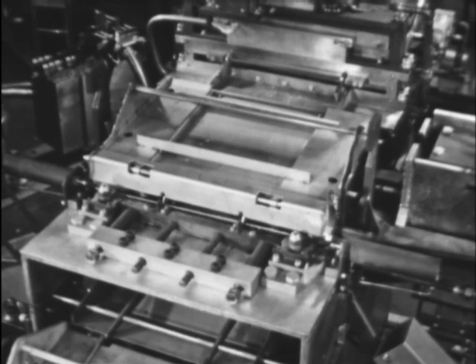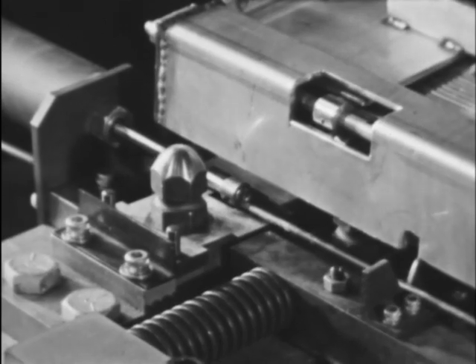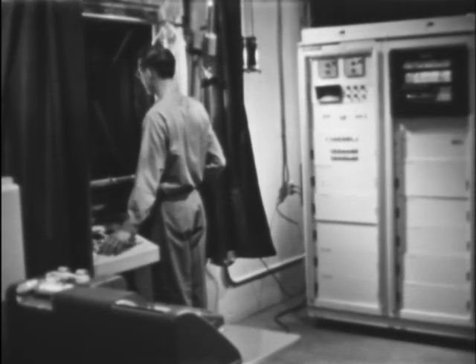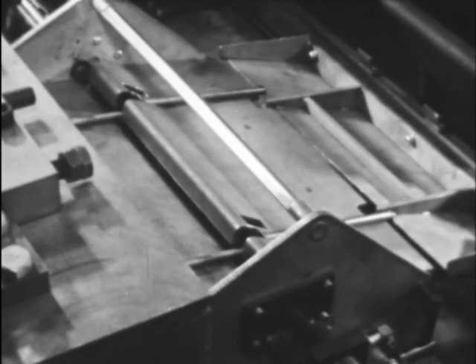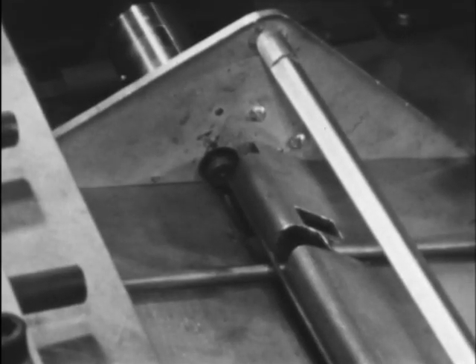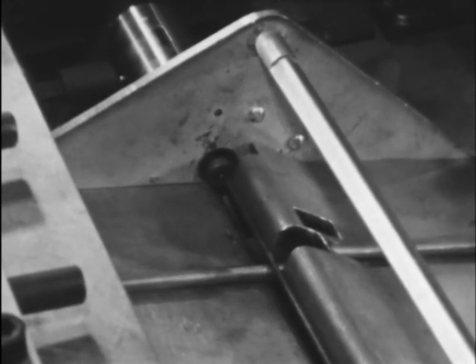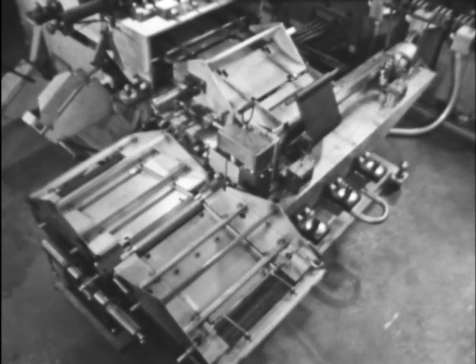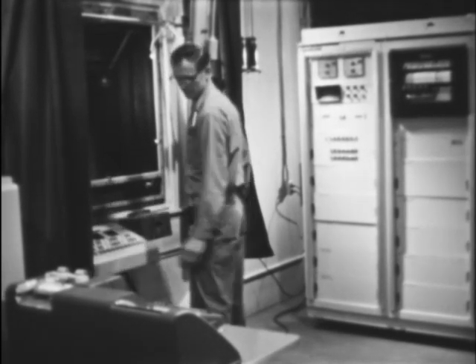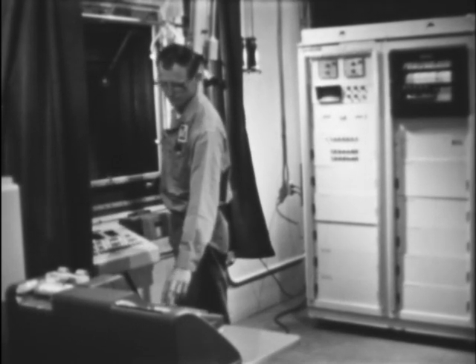The pin's length is measured electrically and weight determined on a remote reading balance. Imperfections are determined by an eddy current device and the diameter gauged. The electrical signals of these inspection devices are fed to a data processor which plots diameter and internal porosity indication along the length of the fuel pin, prints length and weight, and calculates volume and density.